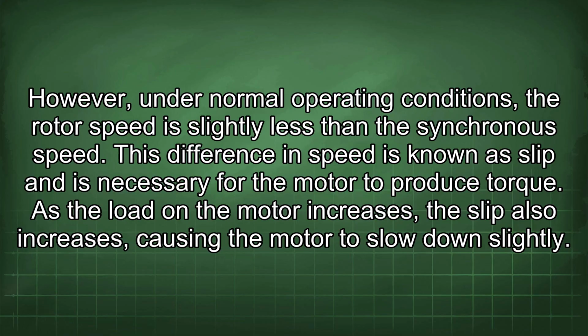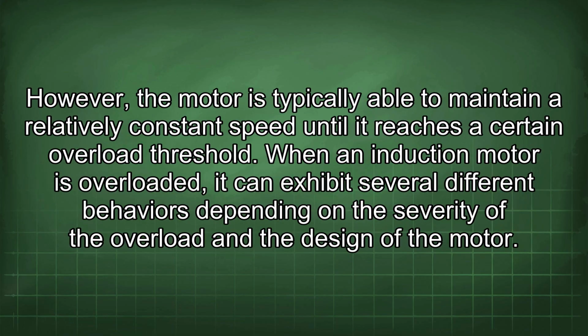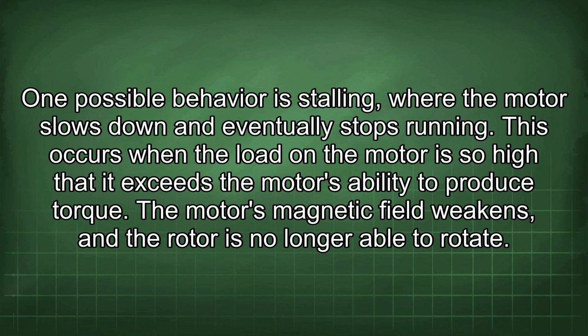As the load on the motor increases, the slip also increases, causing the motor to slow down slightly. However, the motor is typically able to maintain a relatively constant speed until it reaches a certain overload threshold. When an induction motor is overloaded, it can exhibit several different behaviors depending on the severity of the overload and the design of the motor. One possible behavior is stalling, where the motor slows down and eventually stops running. This occurs when the load on the motor is so high that it exceeds the motor's ability to produce torque. The motor's magnetic field weakens, and the rotor is no longer able to rotate.